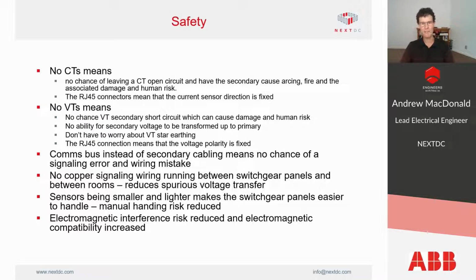The safety. No current transformers means that there's no chance of leaving a CT open circuit and having the secondary cause arcing, fire and the associated damage and human risk within the switchboard. The Rogowski coils also have RJ45 connectors that mean that the current sensing direction is fixed, so you don't have to worry about the polarity of CTs.